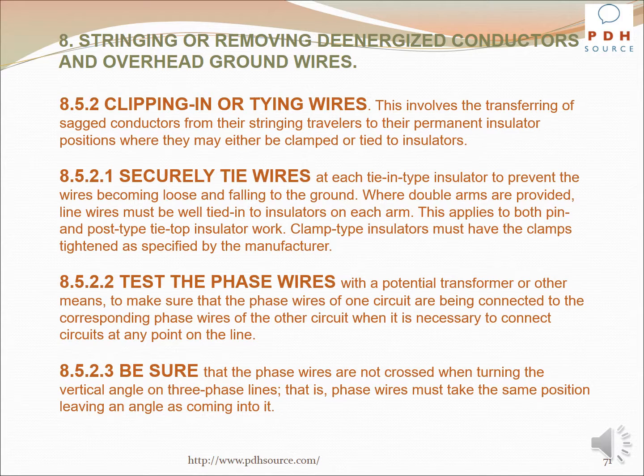Test the phase wires with a potential transformer or other means to make sure the phase wires of one circuit are being connected to the corresponding phase wires of the other circuit when it is necessary to connect circuits at any point on the line. Be sure that the phase wires are not crossed when turning the vertical angle on three-phase lines. That is, phase wires must take the same position leaving an angle as coming into it.